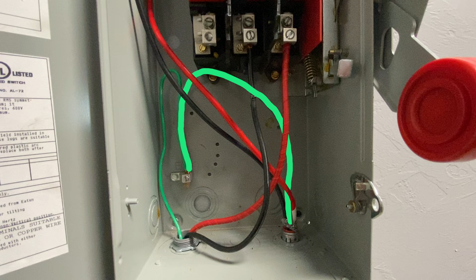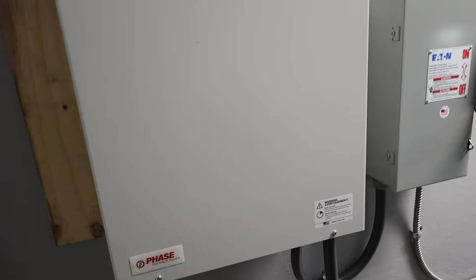This switch box is pretty straightforward. The green ground wire connects to the metal box, then passes through. The electrician used red electrical tape to change the color of the white neutral wire to red. The red and black wires go up to the top of the switch, through the switch, and back out the bottom. From the emergency switch, we go to the phase converter.